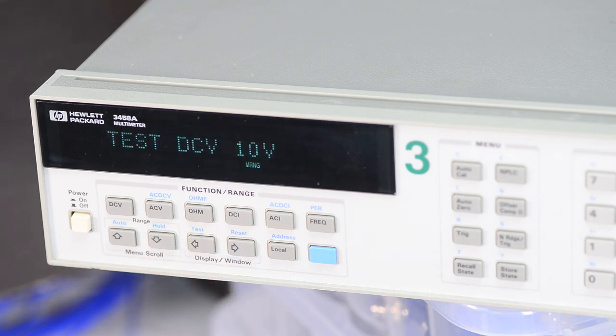So we can do the full self-test by executing it with the blue shift and reset button. It takes about 70 seconds or so to complete the full test. And if the board were not functional at all, it would fail right away. But here we have mostly working. So hopefully everything is good. Now, a passing self-test does not mean the board is not drifty or does not have some smaller issues. It just means that the wide margins for the basic functionality test are met. So this does not mean that the instrument is fully 100% working.